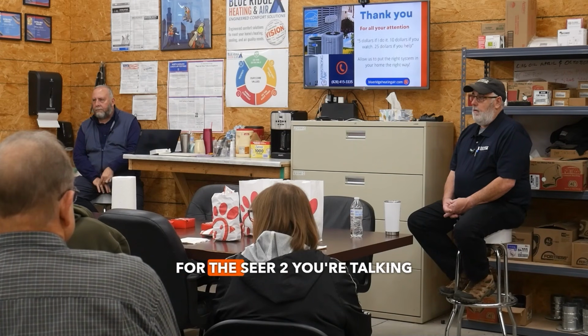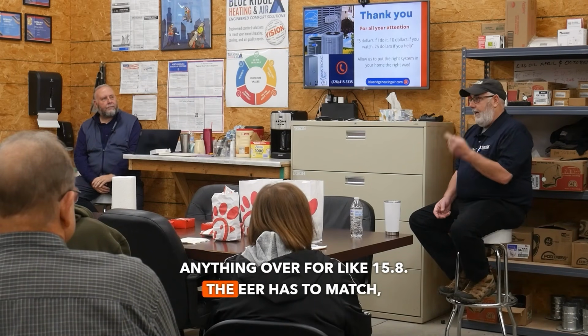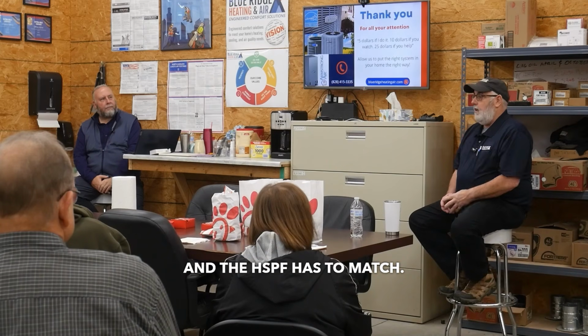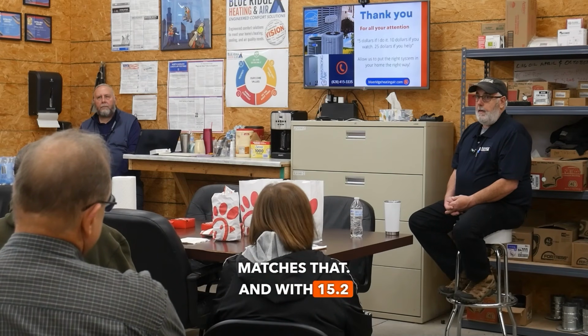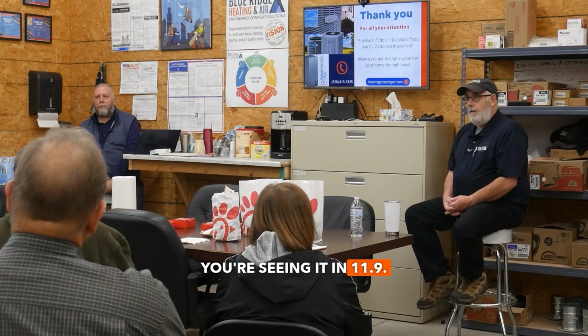Is that for the SEER 2 you're talking about? Yes, anything over like 15.8. The EER has to match, and the HSPF has to match. There's a certain level once you get above that. But even still, our single stage equipment that we're installing matches that. Minimum was 15.2 SEER and 11.7 EER, so that's the minimum. And our units are 15.8 and 11.9. 12.2. 12.2, yeah, they're right.